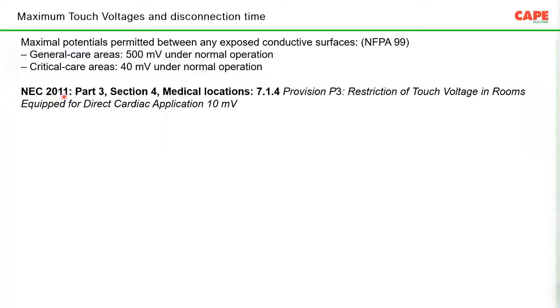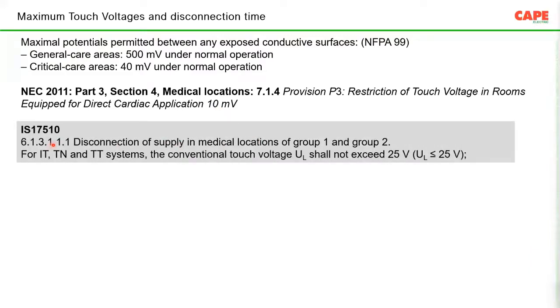The NEC 2011, I mean the National Electrical Code of India 2011, Part 3, Section 4, medical locations, explains the requirements very well, in a detailed way. According to this standard, under certain areas, a voltage of less than 10 millivolt under certain conditions is also necessary to avoid shock hazard. Similarly, the new medical location standard IS 17510, 2020-21, clause number 6.1.3.1.1.1, disconnection of supply in group 1 and group 2 medical locations.